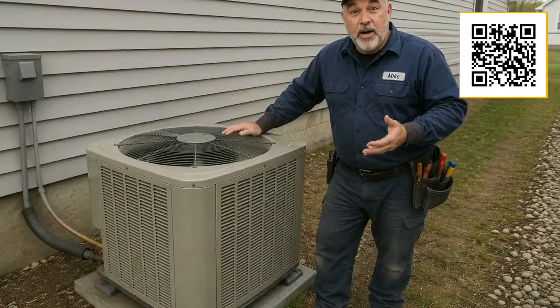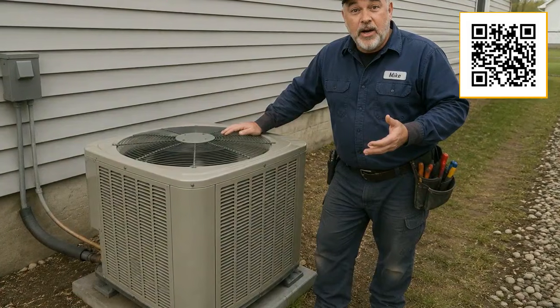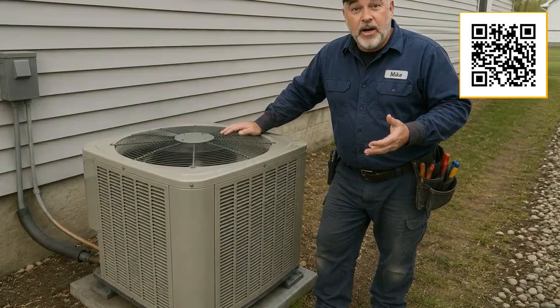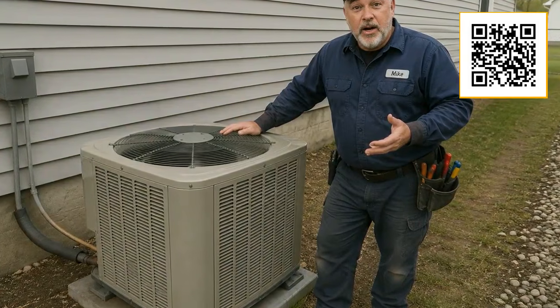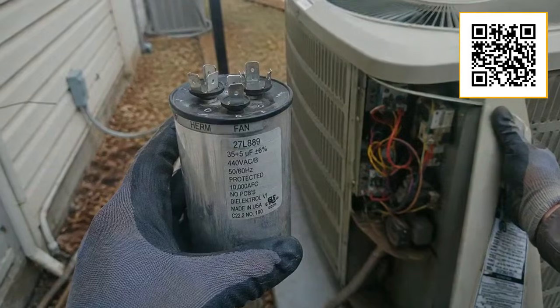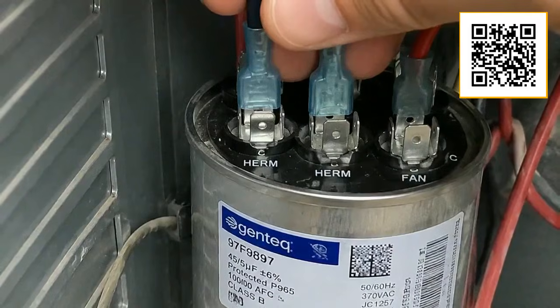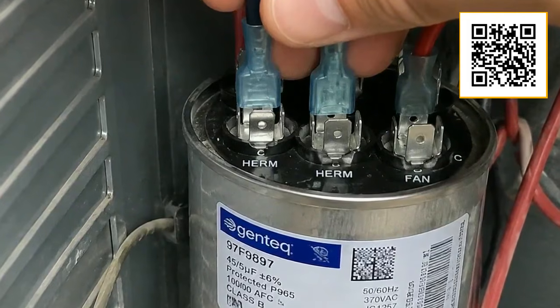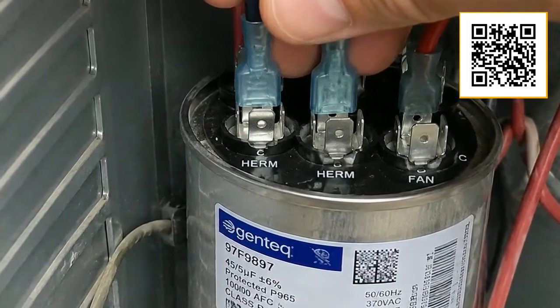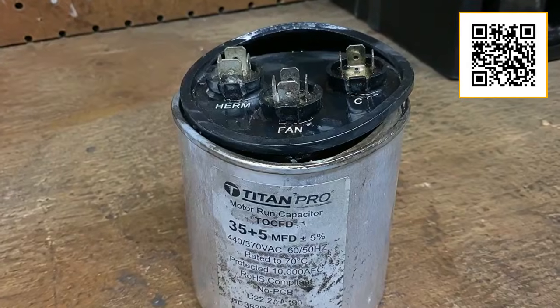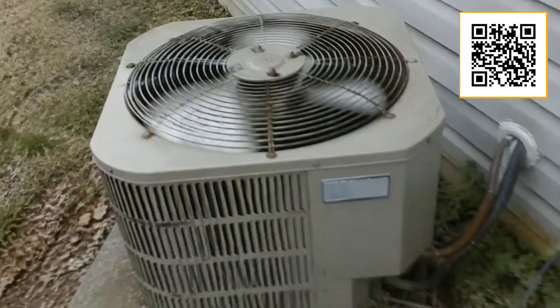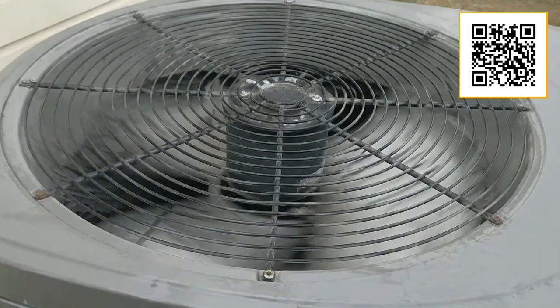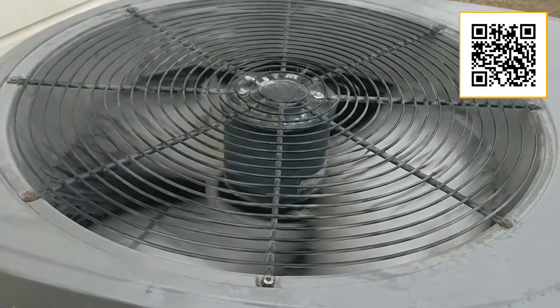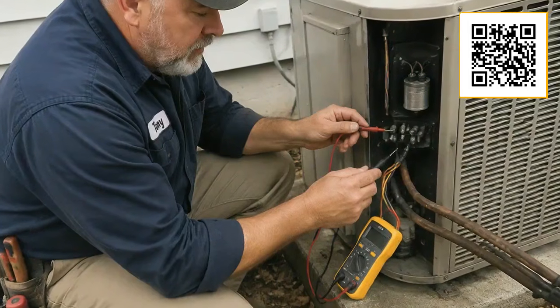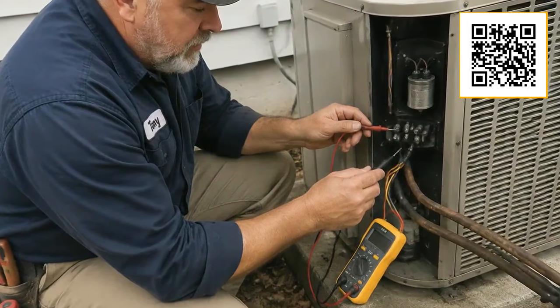Eighth, and I see this one constantly, units with failed or failing capacitors that never got caught in time. The capacitor is a small, inexpensive component that helps the motors in your AC system start up and run. It wears out over time. When it starts to weaken, the motor has to work harder to start and run, which puts stress on the motor itself and on the compressor.